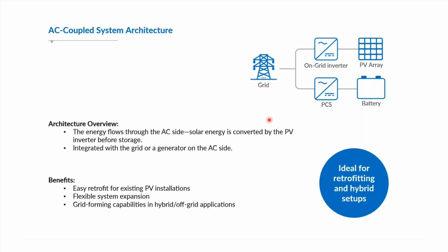This architecture is particularly useful for retrofits. For instance, if you already have solar panels installed with a grid-tied inverter or microinverter at your house, and you now want to add storage, this is the solution to go. In that case, you don't need to touch the DC side of the system at all, you just step into the existing AC infrastructure, and the new components will be blended into the system. That's one of the biggest strengths of AC coupled systems - you can scale, upgrade, or replace components with minimal rewiring.